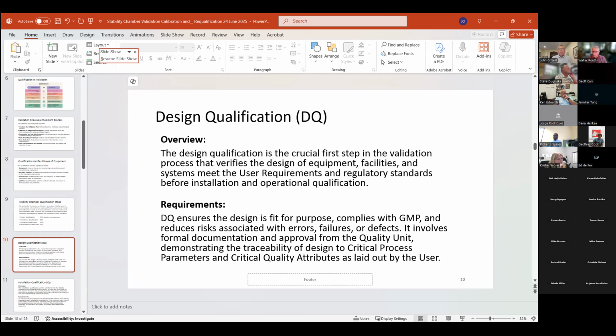Now, we did a previous webinar and went heavily into user requirements, so we won't review those in detail again. But I think the design qualification often holds hands with the user requirements. The designer of the equipment can tell you all kinds of things about that equipment as it lies in your plant, but they also need to know what size doorways that equipment has to move through. Is it actually going to make it into the room? Is the proper electrical connection there with the right level of power? Is the water the proper purity that's going to go into it? So all these kinds of things are listed in design qualification.